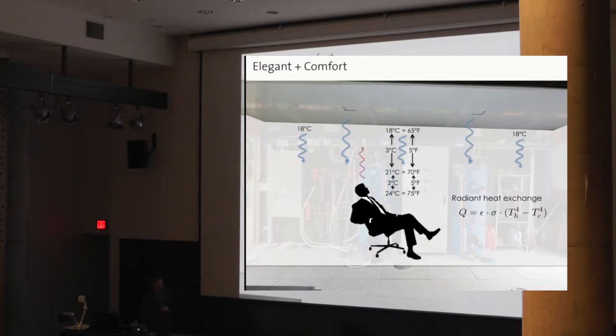The system responds without any control operator, just based on physics alone. On top of that, there's radiant heat exchange - you're not just exchanging with the environment through convection, where the air around you is your proxy for comfort. If I shifted all the surfaces around you in this room by 1 degree cooler, you would think the air temperature had dropped by 1.4 degrees, just because of the physical phenomenon of radiant energy exchange with the surfaces around you. So heat transfers in different ways, and your comfort isn't necessarily about temperature - it's about your body's metabolic rate wanting to be at the most comfortable equilibrium with its environment, through different kinds of heat transfer including radiation.